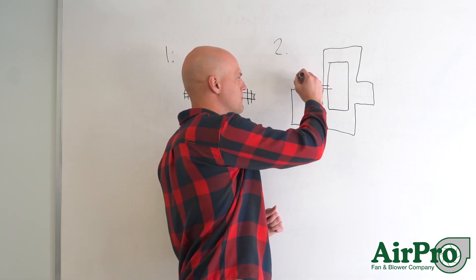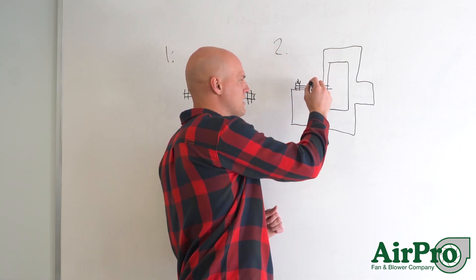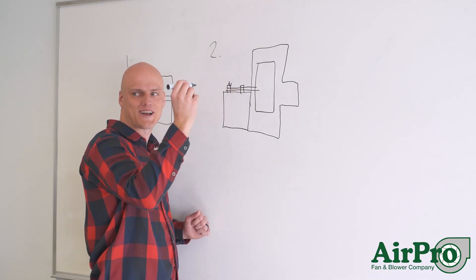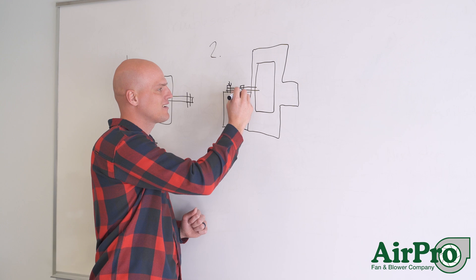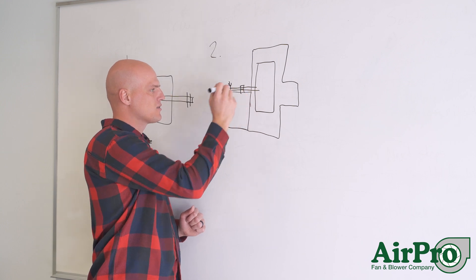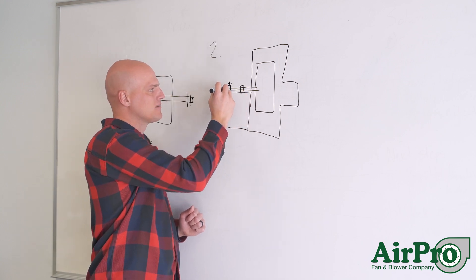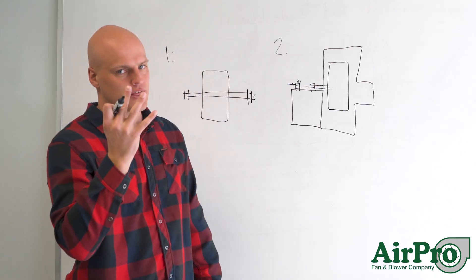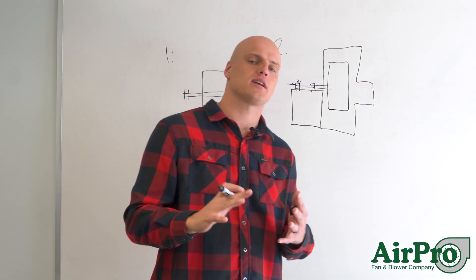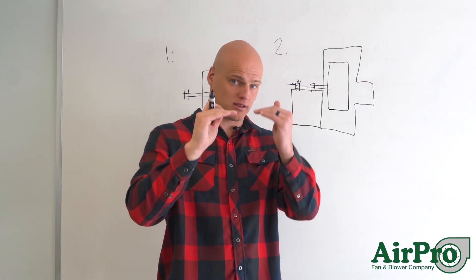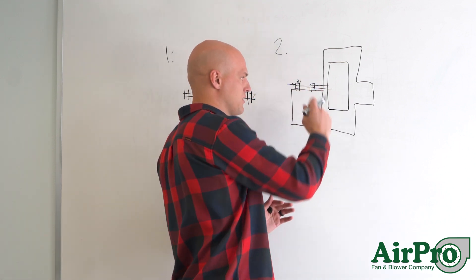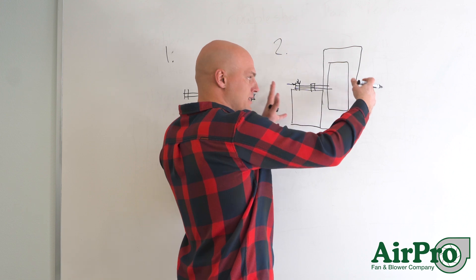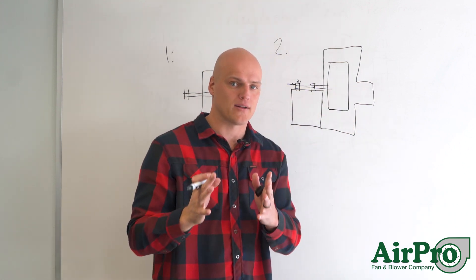In step two, what we're looking at is a vertical, a horizontal, which is directly at the side of the bearing that we're looking at, right here. That's horizontal, and then an axial this way. We're looking at three phases, and we're making sure that it is balanced to within limits in those three phases. And when we have it balanced within those limits, we consider this to be a balanced fan.